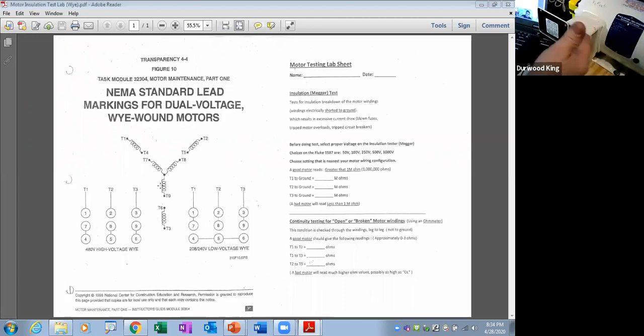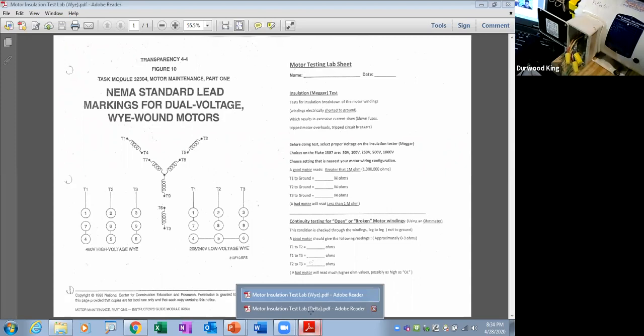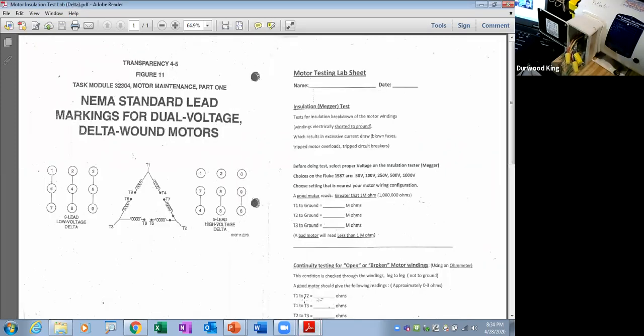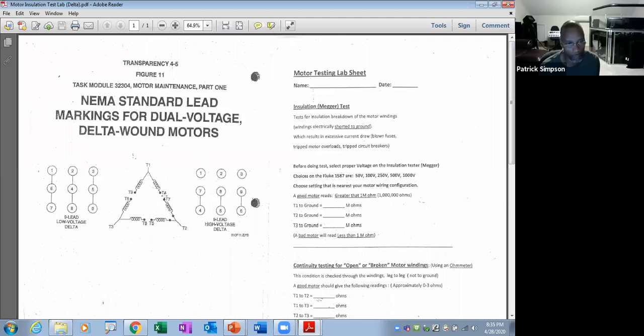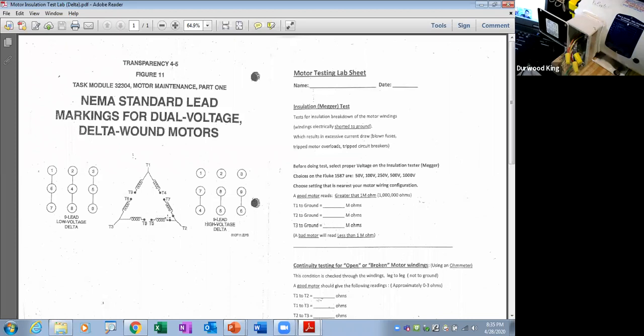If you wonder, is it a Y or a delta? That's how to tell. Now, honestly, if it's a delta, it's actually going to tell you on the motor. So if you go delta, you see the triangle there? Yeah. A delta wound motor, every one I've ever seen would always tell you right on the nameplate that it says delta wound.